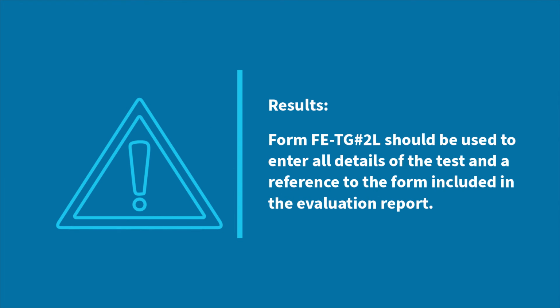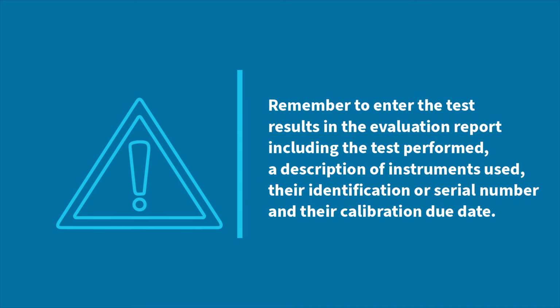Results: form FE, TG, number 2L should be used to enter all details of the test and a reference to the form included in the evaluation report. Remember to enter the test results in the evaluation report, including the test performed, a description of instruments used, their identification or serial number, and their calibration due date. The test is complete. Turn off the ST06, remove the plug from the tester, and then remove the ground clip.